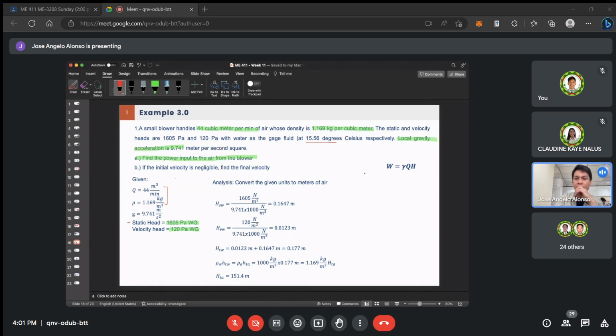So ang kailangan lang natin makuha dito class is the total head. Kasi we have the density already, so makukuha natin ang specific weight. And we have the volume flow rate which is 44 cubic meters per minute. So convert muna natin class yung static head and velocity head in water gauge going to head of air or total head of air para may substitute tayo dito.